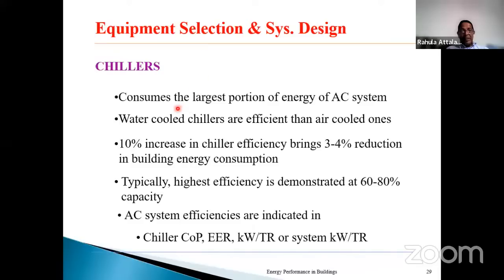Equipment selection. Chillers consume the larger component of AC, and water-cooled chillers are more efficient than air-cooled because of better heat transfer conditions. A 10% increase in chiller efficiency brings a 3 to 4% reduction in building energy consumption. That's very important. That is, if you increase the chiller efficiency by 10%, you can reduce the overall energy consumption by 3 to 4%, based on experience. Typically, highest efficiency is demonstrated between 60 to 80% of the capacity.